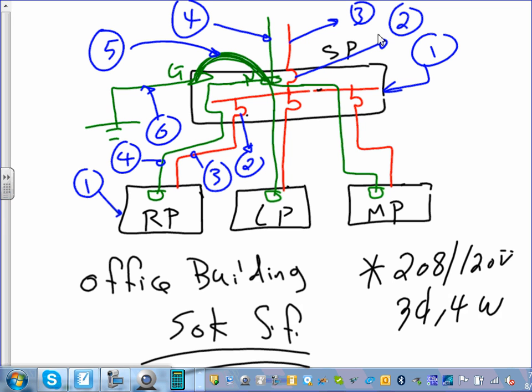Starting with 1, guys, that's the box. The first box is called the service panel. Number 2 is the overcurrent protection device for the service panel, the breaker. Number 3 is the service entrance conductors coming in, the phases. Number 4 is the neutral. Can you see that? That's a neutral. Number 5 is something called the main bonding jumper. You are required by code, when you bring the neutral from the utility, to bond it to the ground for stability, to get rid of transients and to stabilize the neutral. Major thing that you have to do. Every time you bring the neutral, guys, the first thing you do, take a wire and tie it to the ground via a ground rod, or the steel of the building, or a bunch of other things there. Any metallic object in direct contact with earth. That's 5. That's the main bonding jumper.